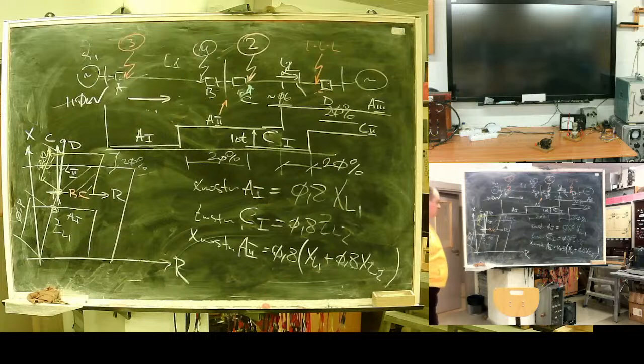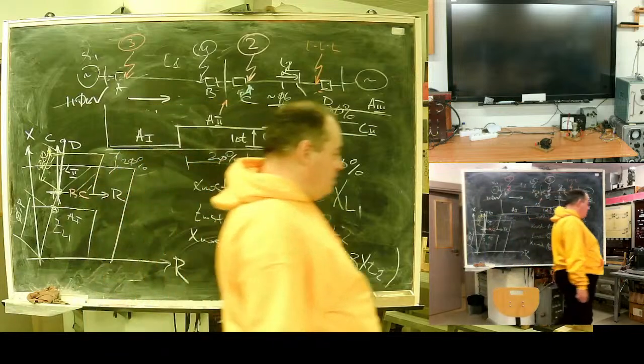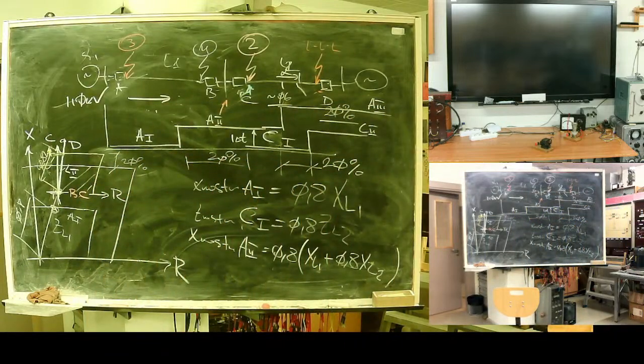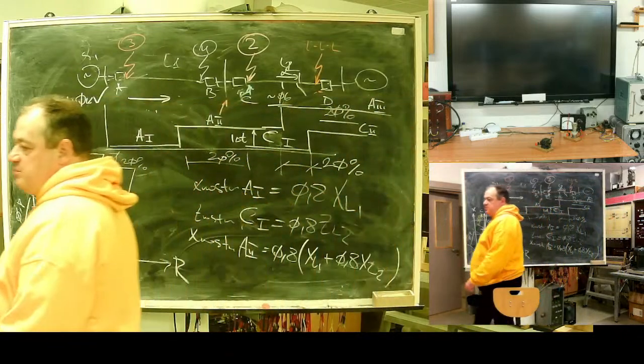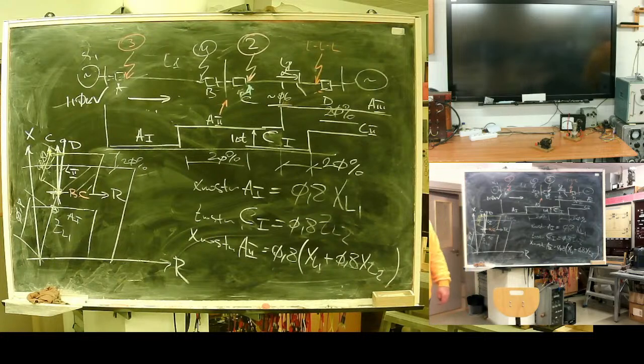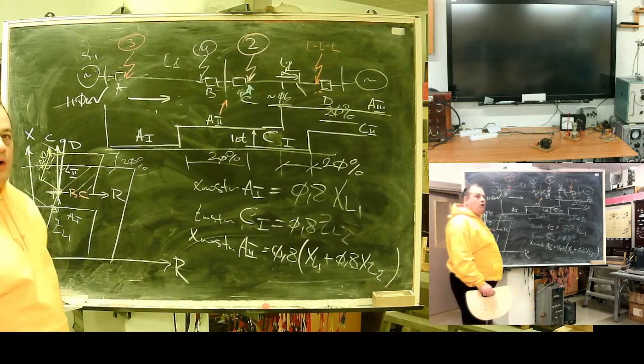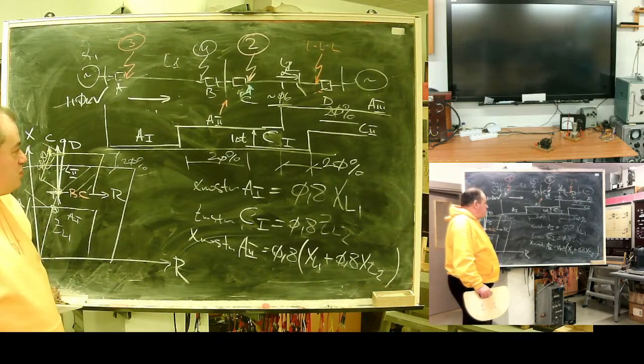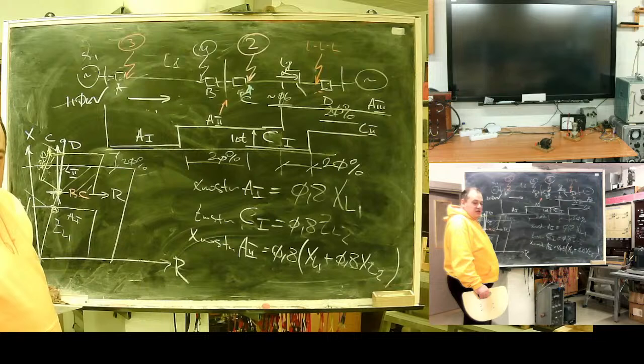Just setting operational resistance something like 80% of minimal possible load resistance. It's in theory, sometimes you can do it, sometimes not. Usually you will have a forward-looking transformer or line and they will set you. The last operational zone should be sensitive. It should be checked against minimal possible load resistance.